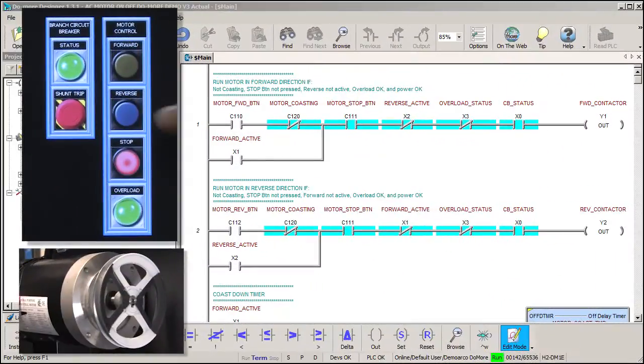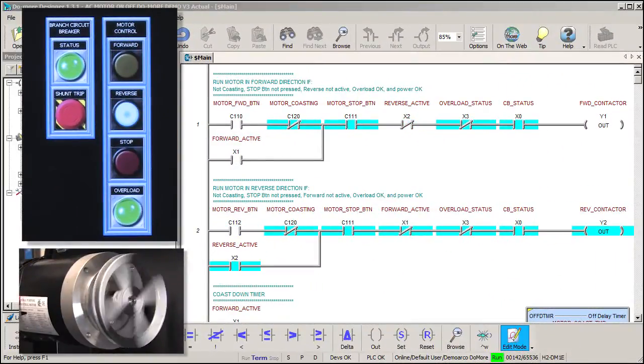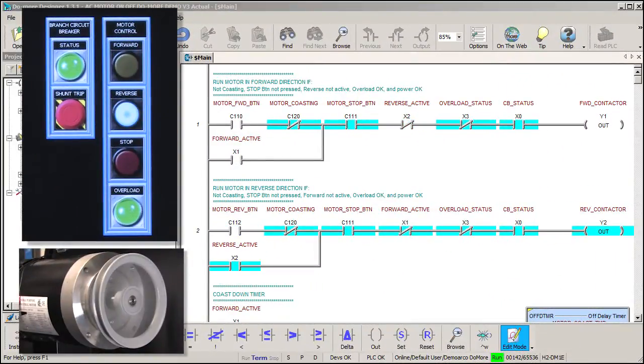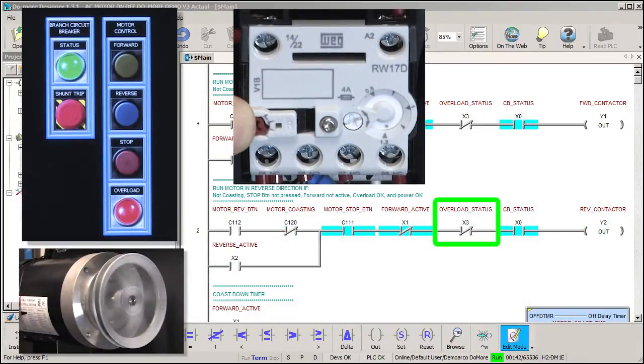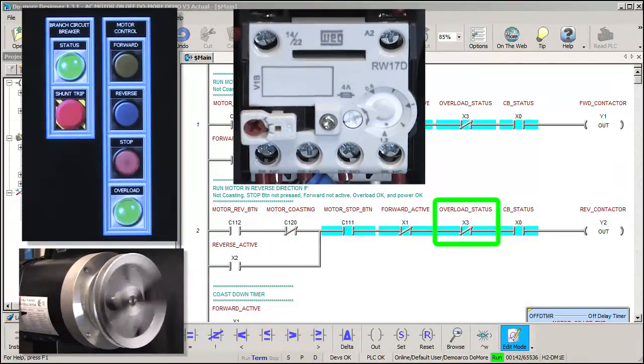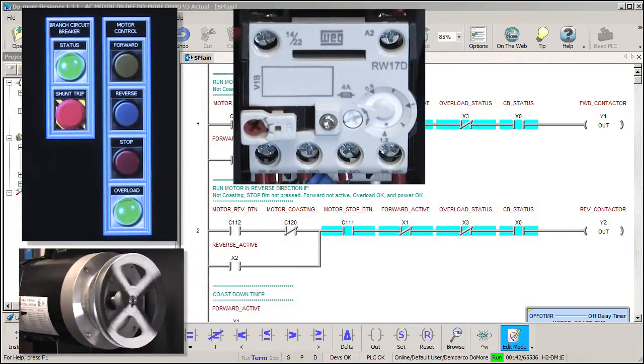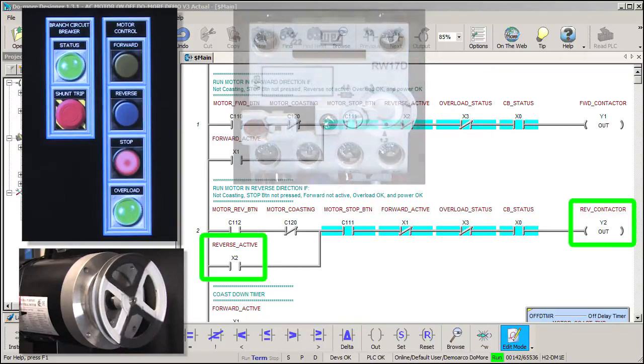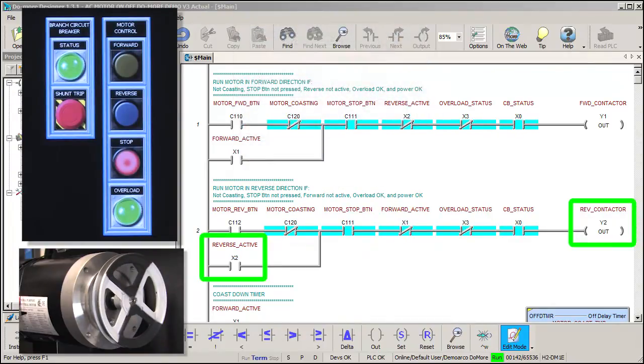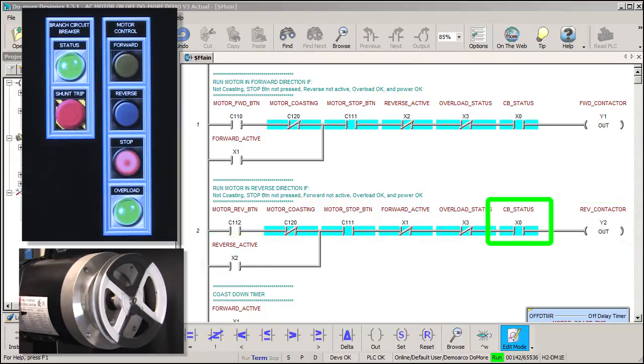Let's start the reverse direction, which works exactly the same as the forward circuit, but this time we'll press the overload test button and sure enough, it deactivates this contact, which disables the contactor and its aux contact, which kills the power to the motor. Exactly what we expected. The circuit breaker aux contact would work the same way.